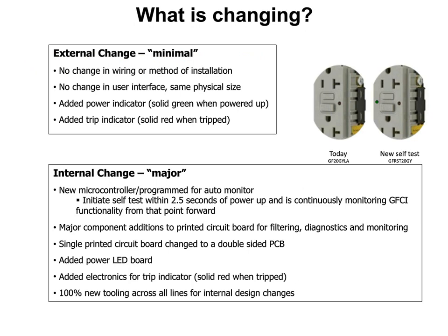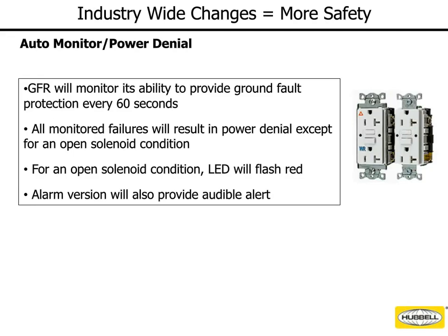So what does that mean to end users? From a pricing standpoint, you can expect the cost of a standard ground fault receptacle to increase by about 40%. It's a significant design change for the manufacturers to redesign those circuit boards and put microprocessors in. So you will see the cost of ground fault receptacles increase, whether it's residential, commercial, or industrial, it doesn't matter. They're all going to go up, about a 40% cost increase. Externally, there's minimal change that you're going to see. You'll see some added LEDs for the functionality to give you power-on indicators and end-of-life indicators. Internally is the major change, where you've got a new double-sided circuit board inside, and it gives us the ability to program it in such a way that we can get that self-testing product line.